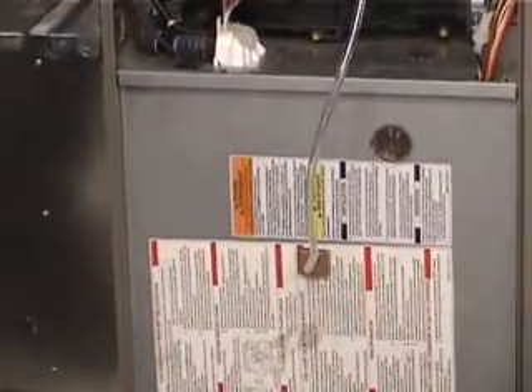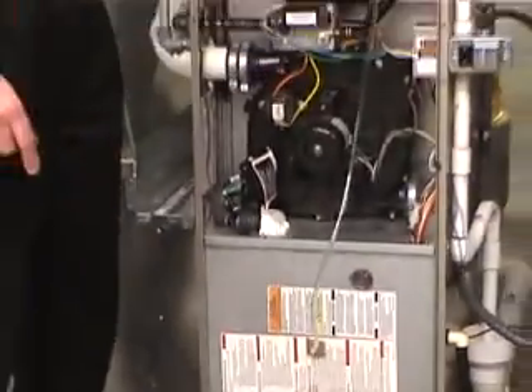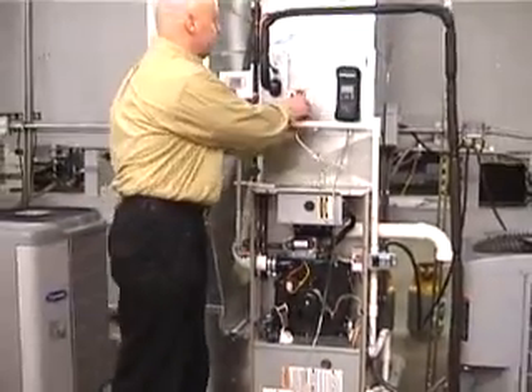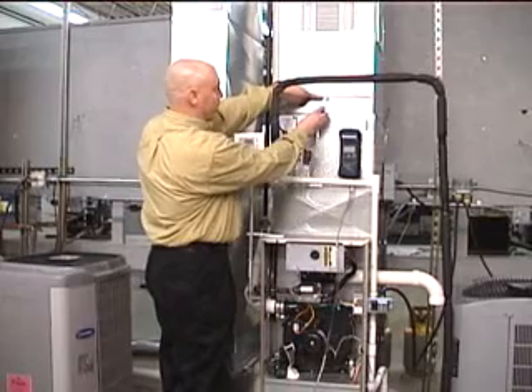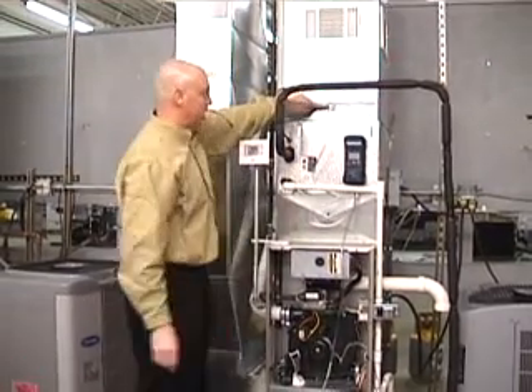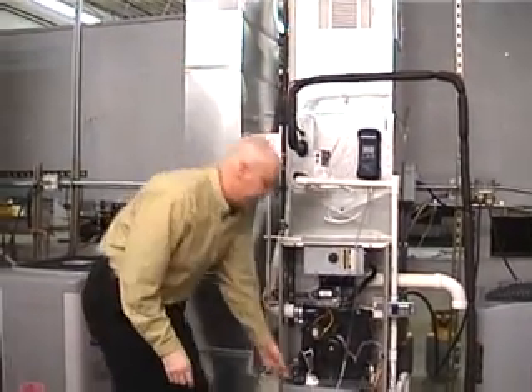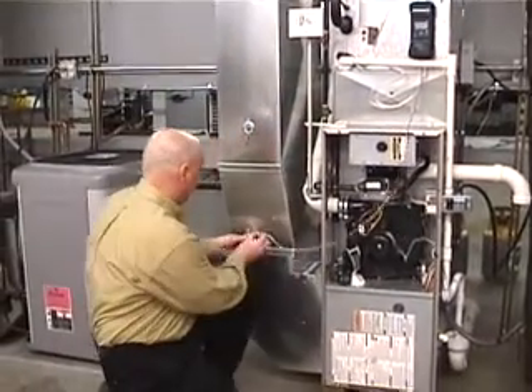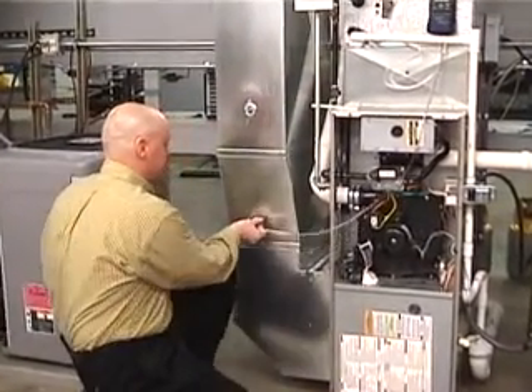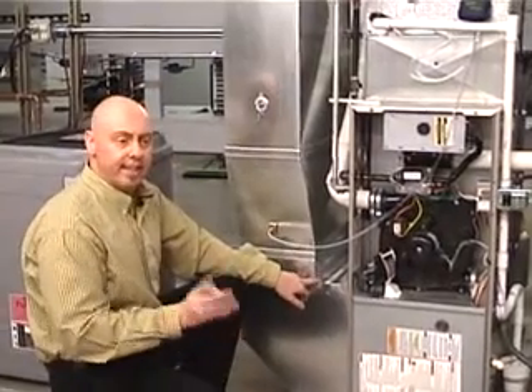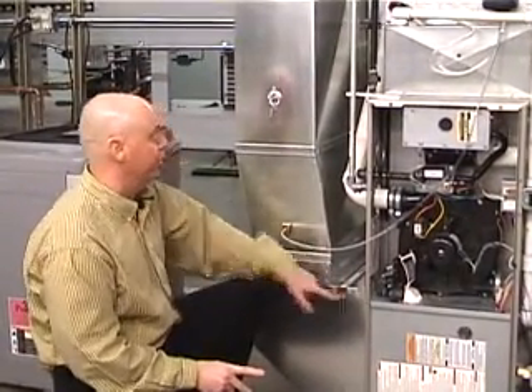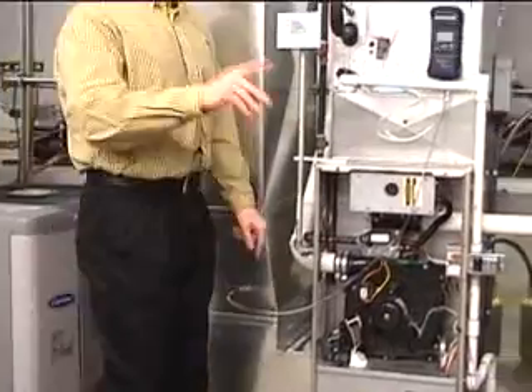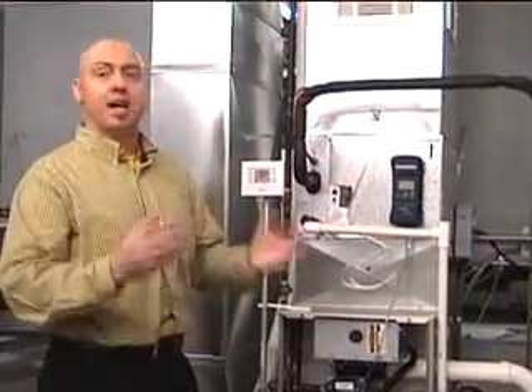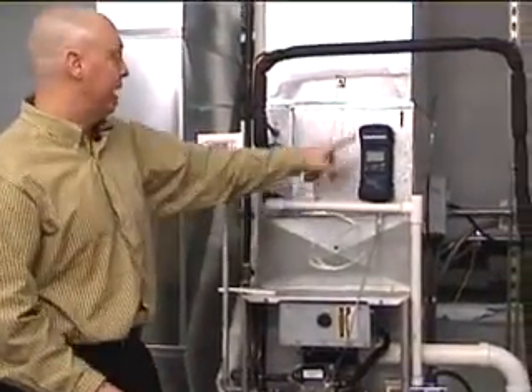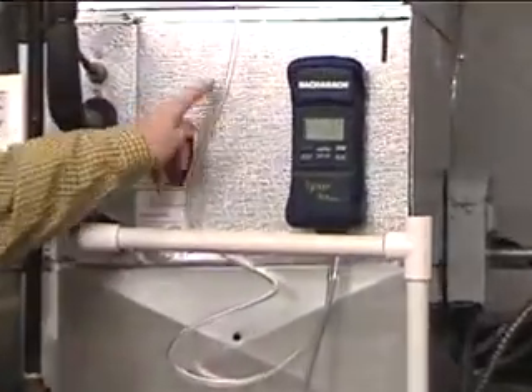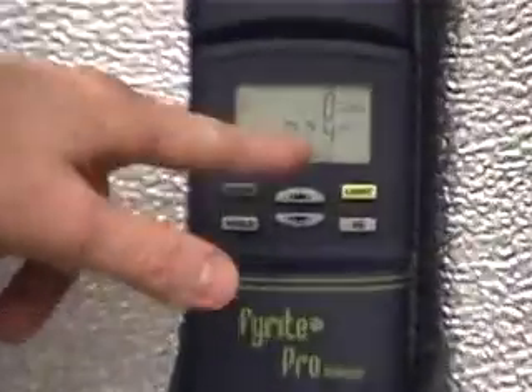But what guys tend to do out in the field is they go to the easier locations. They tend to be on the outlet side of the coil up here in the plenum area, and then they take their other probe and be in the return air drop area. So they're actually not taking into consideration the resistance value of the filter and the coil. Now that same system, that I was just running at 0.55 or 0.52, I don't remember exactly what it was, but you'll see now with these new readings, not including the coil or the filter, I'm running a 0.24.